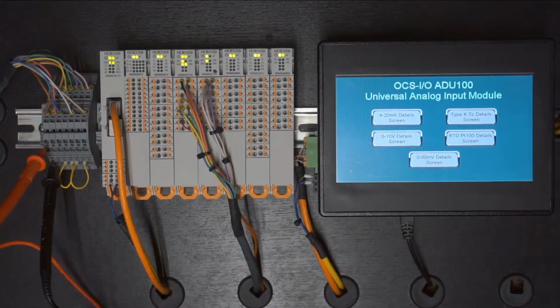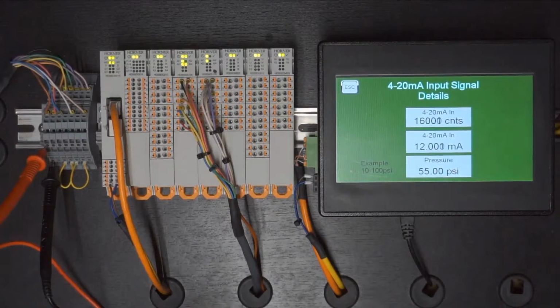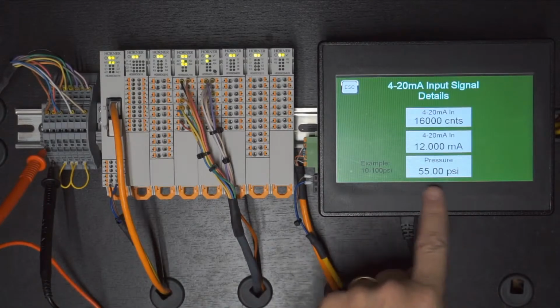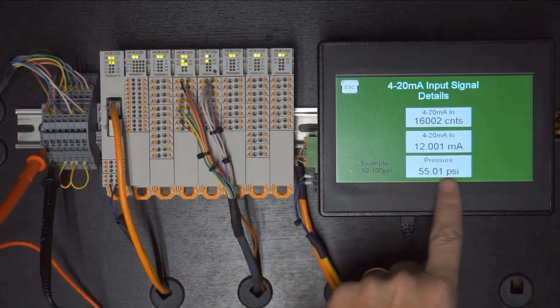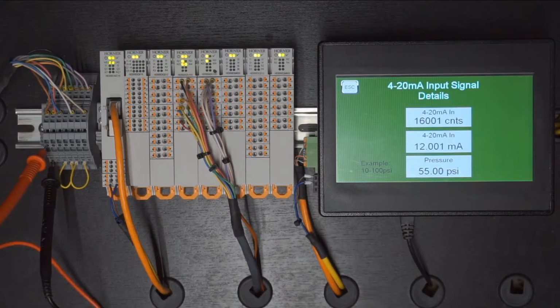So let's start with 4 to 20 milliamps. I'm at a mid-range setting on my simulator of about 12 milliamps. So let's see what things look like. Mid-range would be about 16,000 counts, and we're there within a count or two. Looks pretty good. I am kind of simulating a 10 to 100 pounds per square inch type sensor with a 4 to 20 milliamp output. If I go down to, say, 6 milliamps or so, which should be a fairly low setting, you can see my readings respond. If I go up to full scale at 20 milliamps, you see they respond as well.